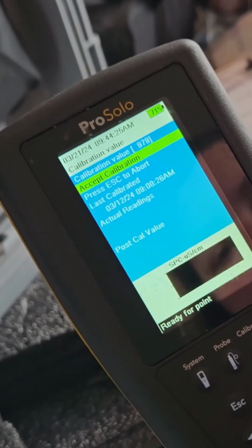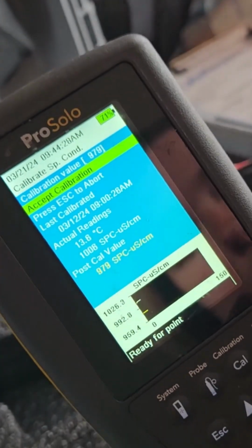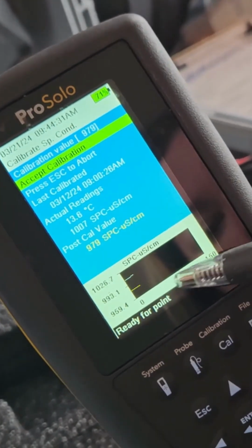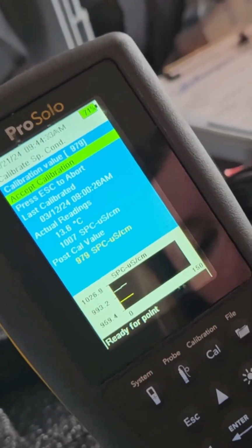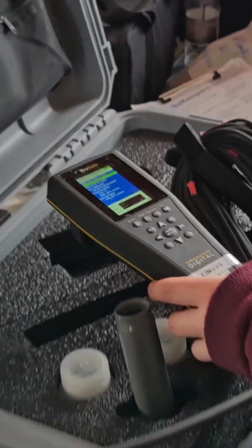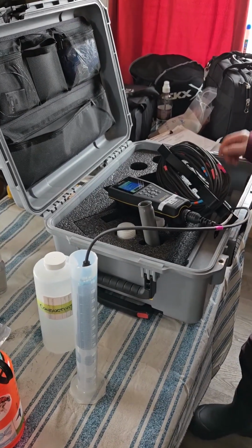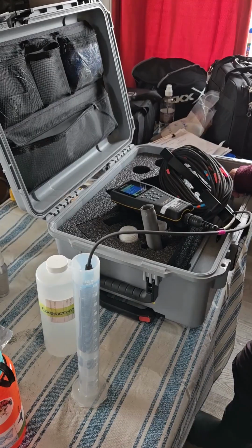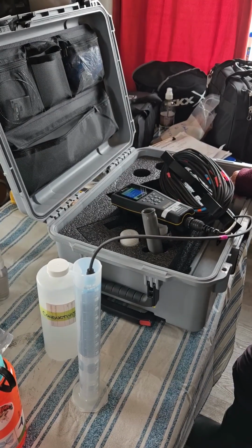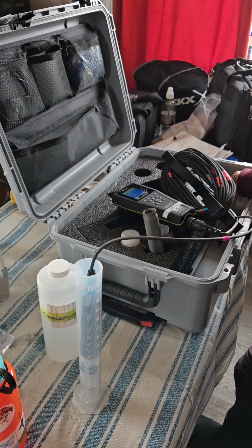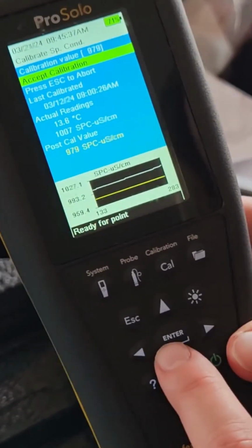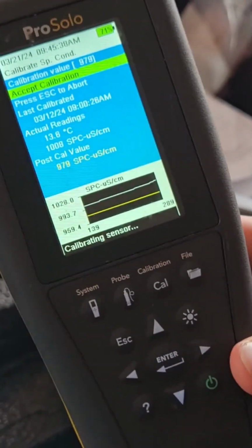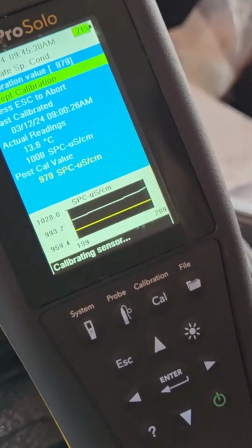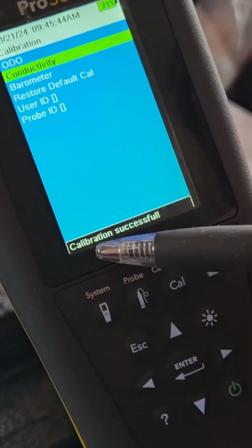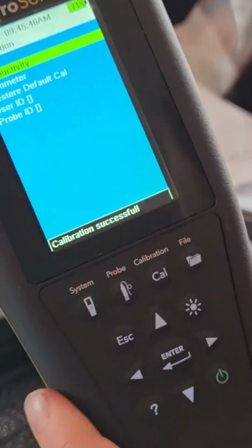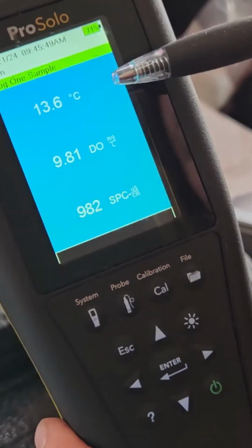We're seeing those lines go across, and we will let that sit for about a minute. And we'll watch those lines, making sure there's no spikes and no bumps so that it's stable. And after a few minutes of making sure that that's stable, we will click accept calibration. We'll see again that it'll say calibrating sensor and calibration successful. We will then return to our main screen.